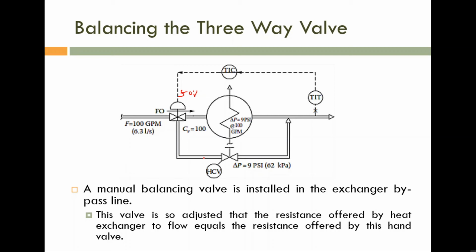But please note, if you are using a balancing valve, definitely the cost will increase. That is a problem. But we have to use this valve if the resistance offered by the heat exchanger is dominant. So this is the additional explanation that we have.